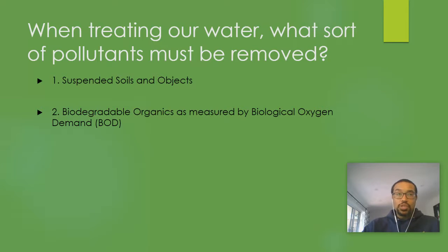So, microbes are introduced into the process, and those microbes will actively eat away at organic material that's in our wastewater, and they will consume a very large percentage of that organic waste before a final treatment is done to kill organics that we don't want, microbes that we don't want, before the water is returned to the river. And that's measured by something called biological oxygen demand. And what that looks at is the amount of oxygen that's being consumed by aerobic microbes. So those are microbes that do their work in an oxygen environment. They consume oxygen in order to eat that organic material.